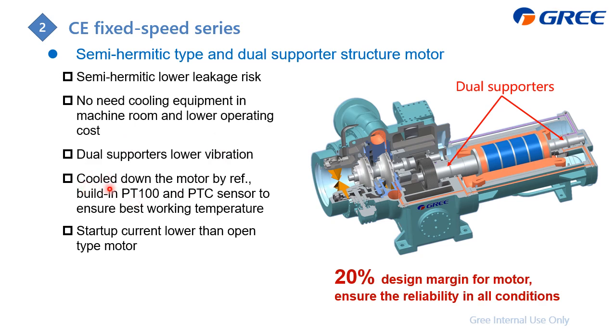And we also use PT100 or PTC to ensure the motor temperature is not too hot, not too cold, to ensure the operating efficiency. And as for the startup current, because this one is semi-hermetic, the startup current is lower than the open type. And from the design, there is 20% design margin for the motor, which can ensure the reliability for all conditions, which means for the surge as well.